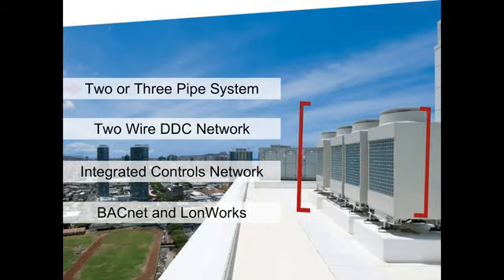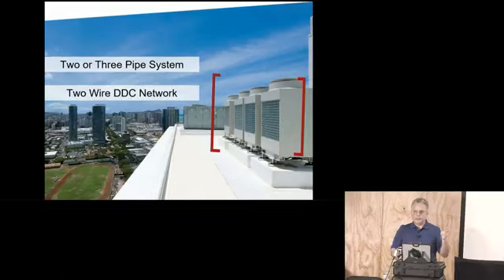So there are 2 or 3 pipe systems, 2-wire digital direct control network, which is just, it could be shielded or unshielded cable, and you just daisy chain, and that's the communication system. Some manufacturers are polarized, so you have to land them at the specific terminals. Others are non-polar, so it doesn't matter.